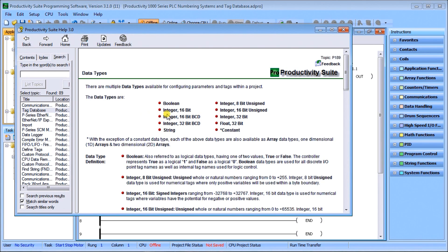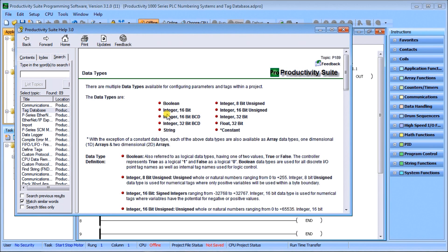Then we have integer 16-bit signed, and the range is minus 32,768 to 32,767. It's used for numerical tags where variables have the potential for negative or positive values.